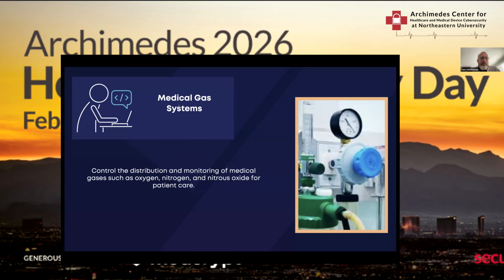Your medical gas systems, oxygen, nitrogen, nitrous oxide for patient care, things like that. Those are your big tanks, usually in the back of your building or off the side, painted white, big cryogenic tanks, or you might have some sort of compressor in there to make your own oxygen or nitrogen. They are all controlled by programmable logic controllers, PLCs, or some sort of embedded device. These embedded devices are locked into a control cabinet somewhere, with an Ethernet cable connected to them, or might have a cellular connection back to the supplier. When that level gets low, they come out with a truck and fill it. It's magic, it just happens. However, what happens when that doesn't happen? Your cellular connection or wireless connection, however that's getting back to your supplier, no longer makes it, or that number is changed.